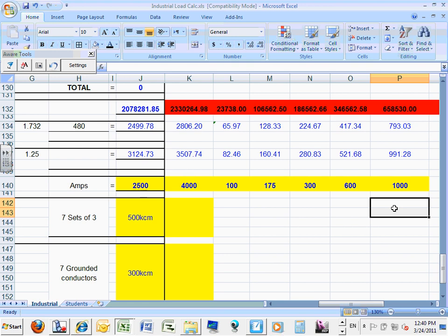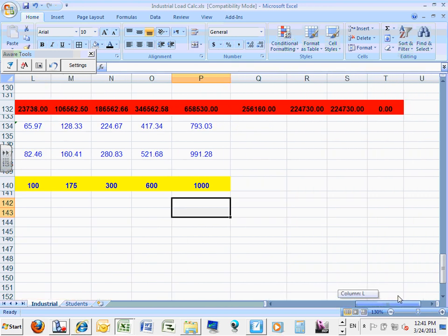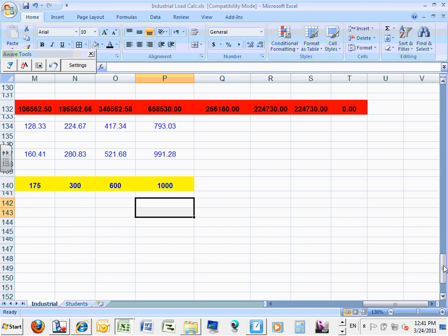Guys, this sheet, gentlemen, this sheet is a living object. As we start designing, it starts making more sense when you see the 480 busway and the 208 busway. I just sized a big chunk of plug-in busway that's coming to the area. And I'm not going to lie to you, if you drag them across, I can't remember what the other panels were.